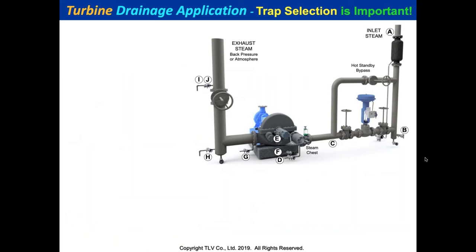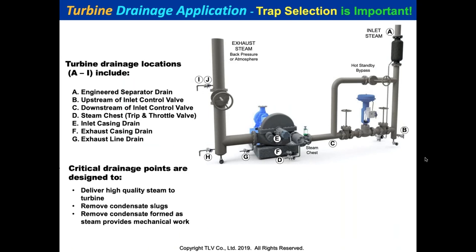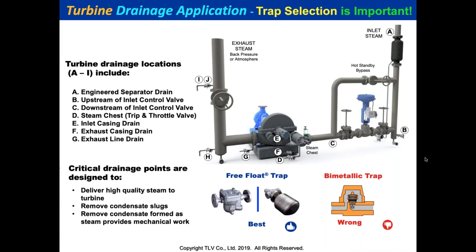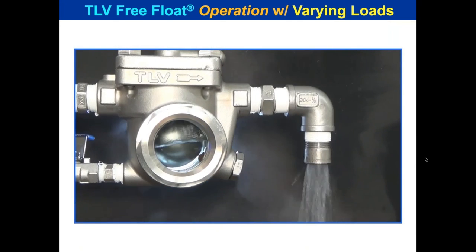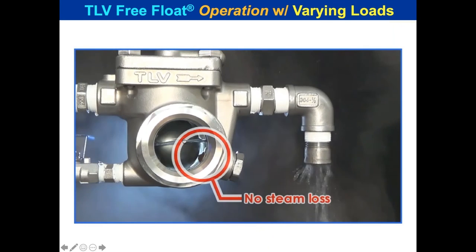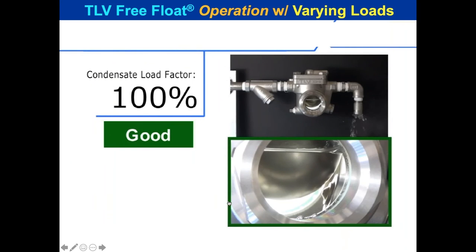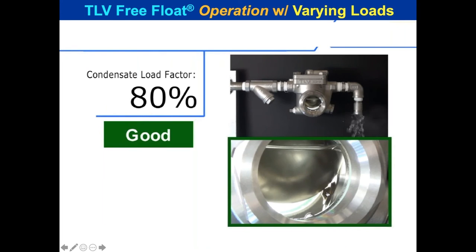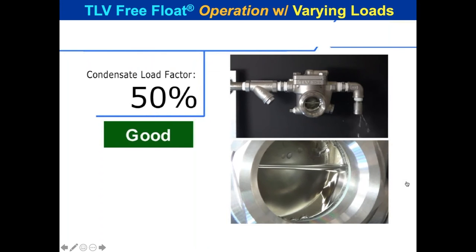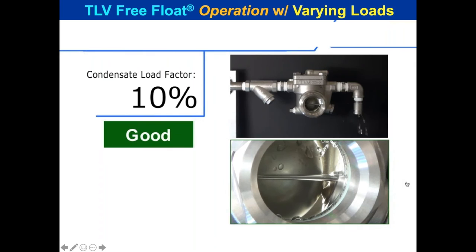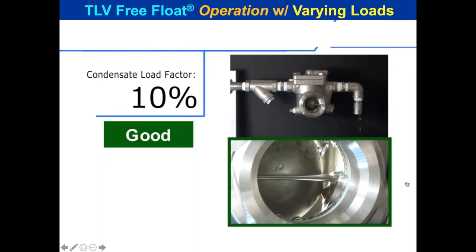We would never allow you to use one of our bimetal traps on a turbine system — we recommend free float traps. A free float trap with a window shows it maintains a water seal, always keeping steam at the top. Whether at 100%, 80%, or 50% of load, it always keeps a water seal over the orifice. The models we use for turbines are good for superheat — they have three-point seating for tight sealing even under superheat conditions.